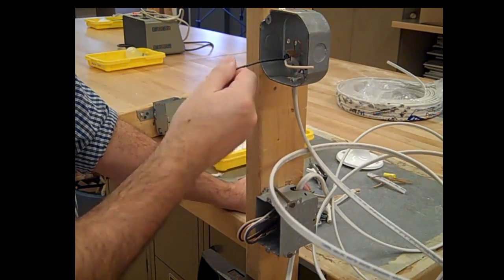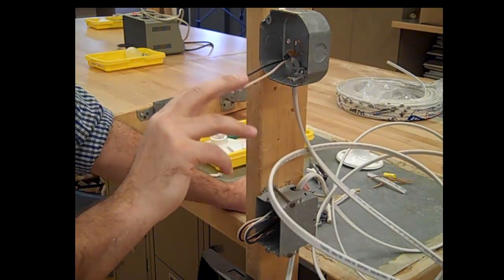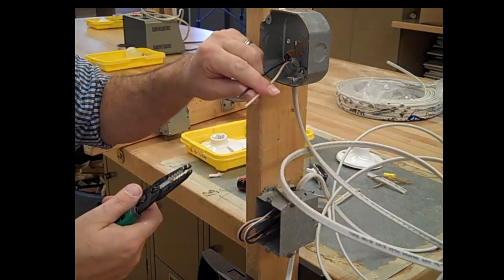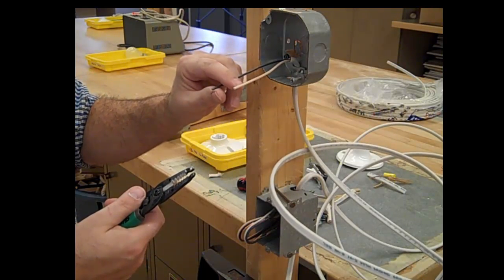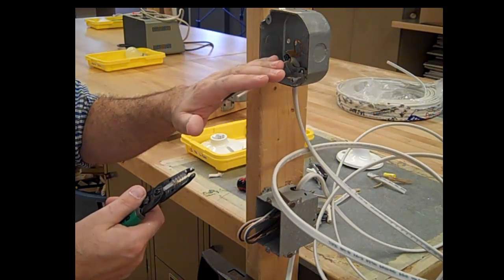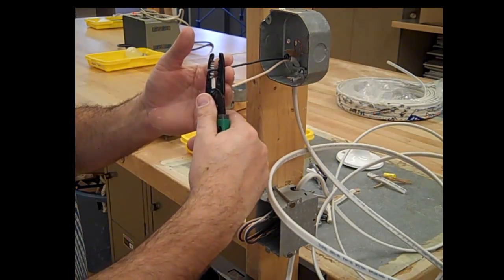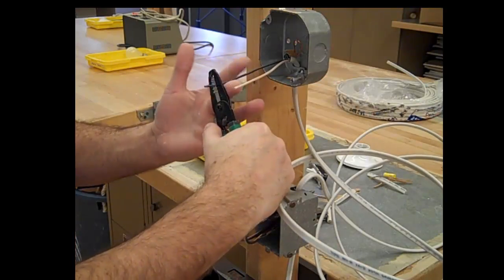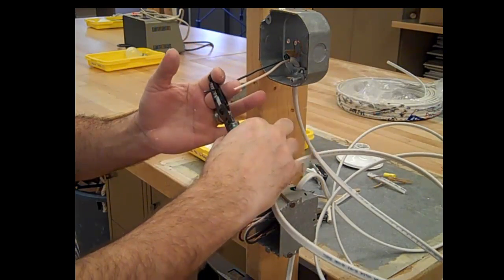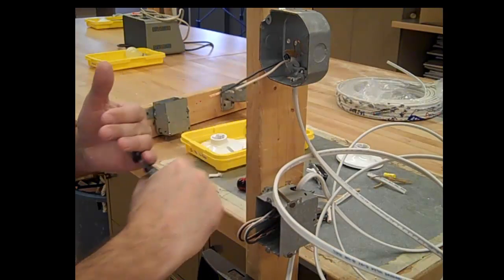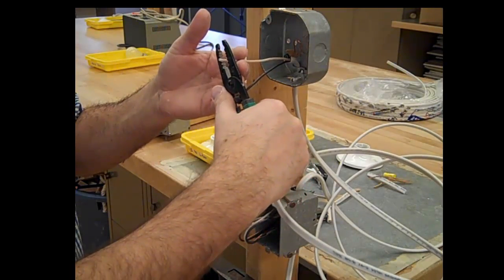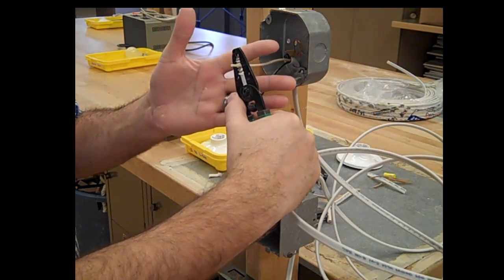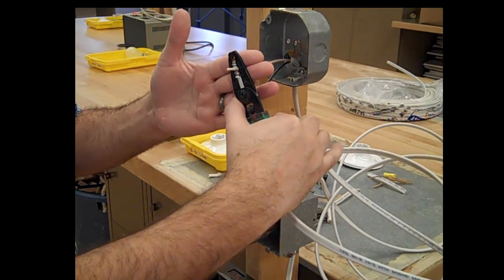The next thing we're going to do is strip back the ends of these two wires using wire strippers. This is 14 gauge wire. You're going to line it up with 14, go back about the thickness of your finger, squeeze, turn, put a finger on each side of the wire, loosen this hand just a little bit, wiggle and pull.